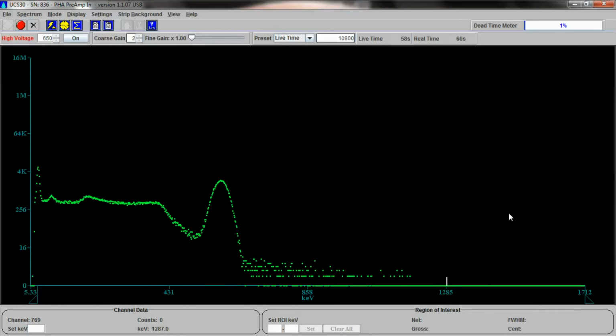Okay? Now, it's always best when testing for an isotope to calibrate with the isotope you're testing for, but you can't always do that. So we're going to do this without that. I have plenty of potassium-40, but I want to show you how to do it without that, because you never know. What if you were looking for plutonium, for example? It's not like you have any of that sitting around, so let's do it.